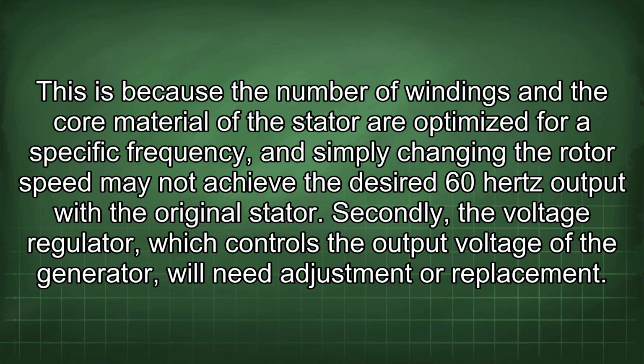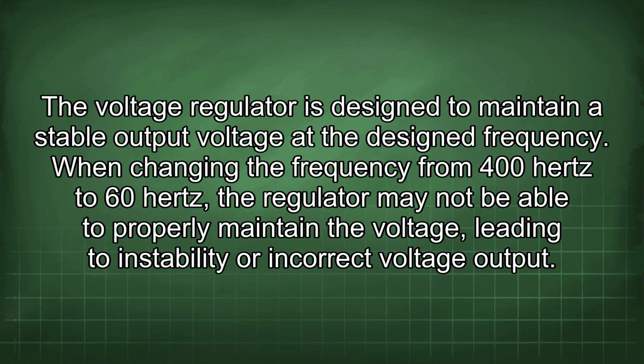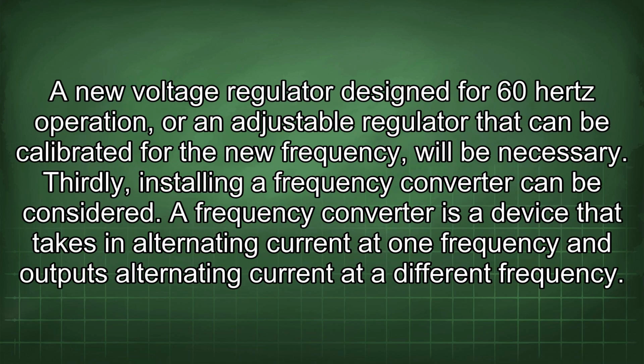Secondly, the voltage regulator, which controls the output voltage of the generator, will need adjustment or replacement. The voltage regulator is designed to maintain a stable output voltage at the designed frequency. When changing the frequency from 400 Hz to 60 Hz, the regulator may not be able to properly maintain the voltage, leading to instability or incorrect voltage output. A new voltage regulator designed for 60 Hz operation, or an adjustable regulator that can be calibrated for the new frequency, will be necessary. Thirdly, installing a frequency converter can be considered.